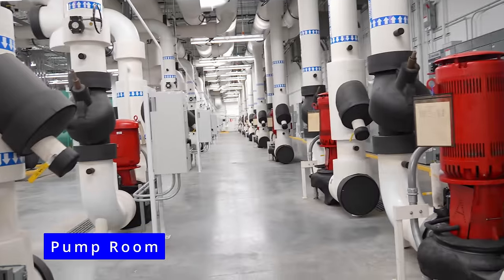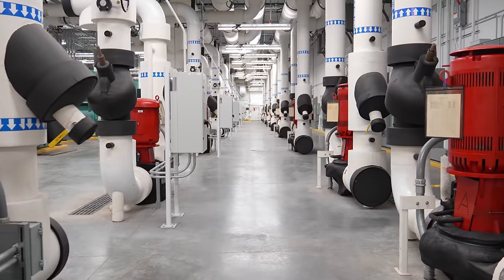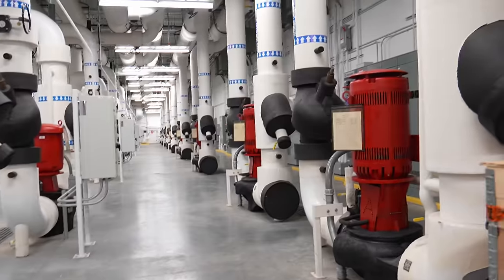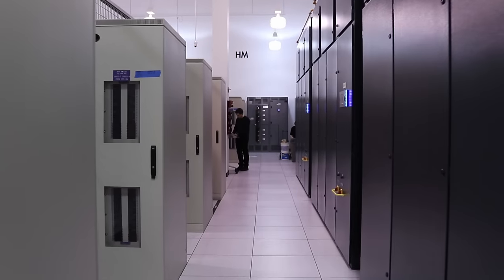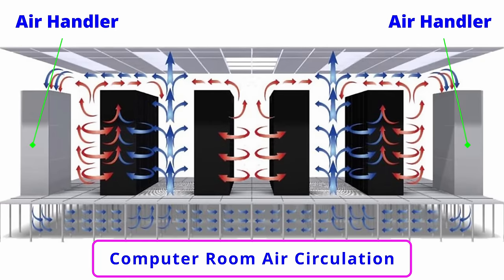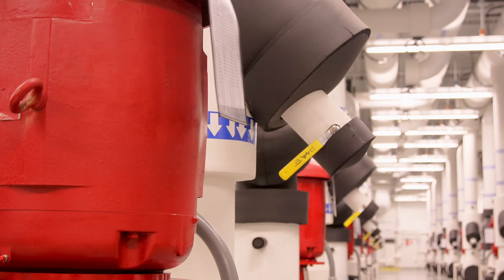This is the pump room for phase one. What you see are the redundant pumps for cooling — circulating coolant from the chiller plant to the cooling loops inside each of the data rooms. The coolant routes up, down, and around underneath, going into every single room. Most rooms have their own independent chain for diversity. The computer room air handlers don't have compressors — they're just large radiators taking hot air, pulling it through to cool it with the coolant, and pushing that coolant back to the pumps.